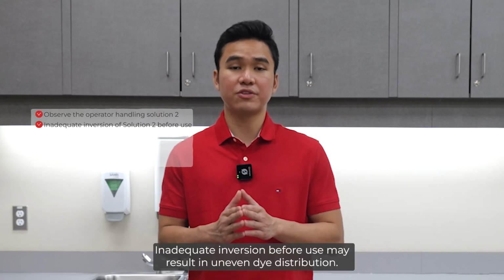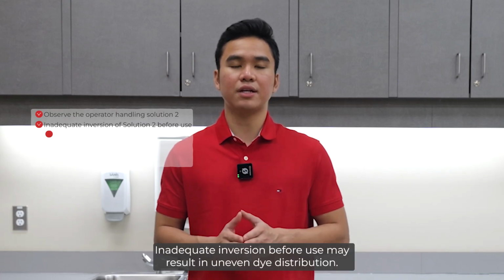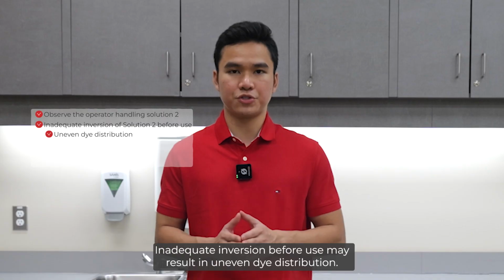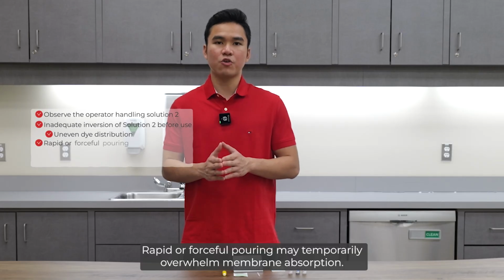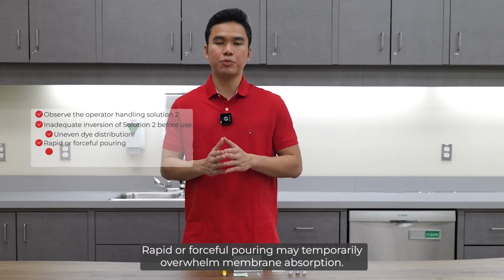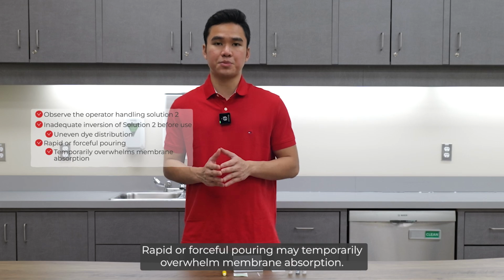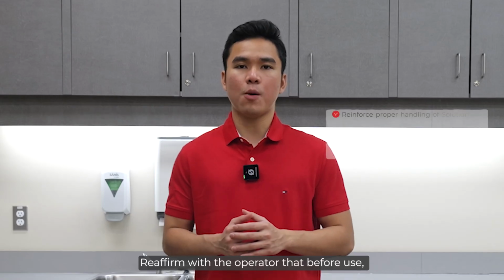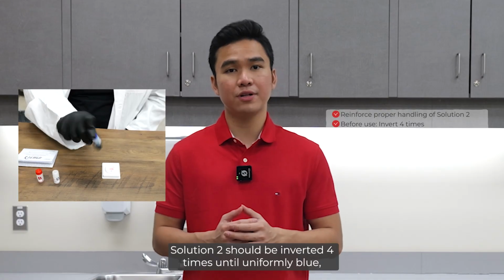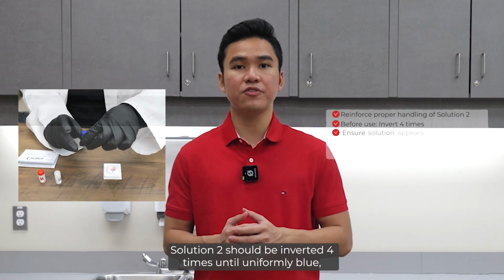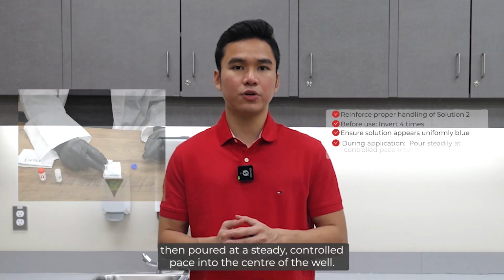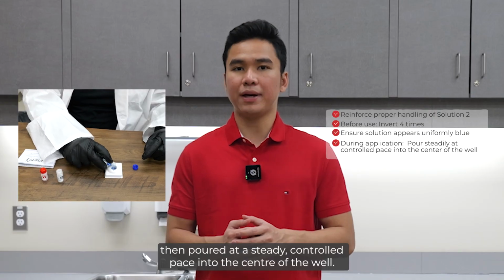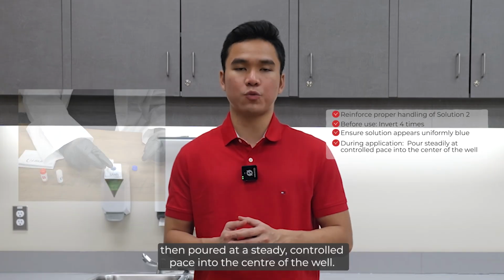Inadequate inversion before use may result in uneven dye distribution. Rapid or forceful pouring may temporarily overwhelm membrane absorption. Reaffirm with the operator that before use, solution 2 should be inverted 4 times until uniformly blue. Then pour it at a steady, controlled pace into the center of the well.